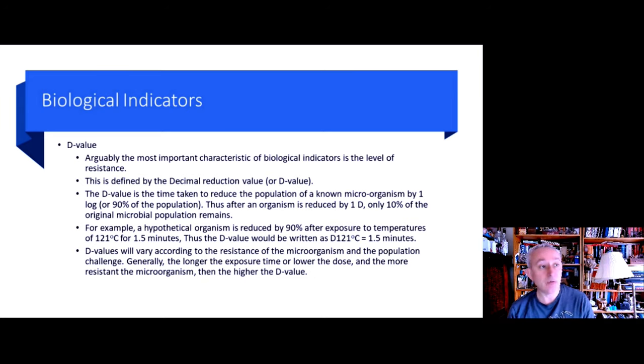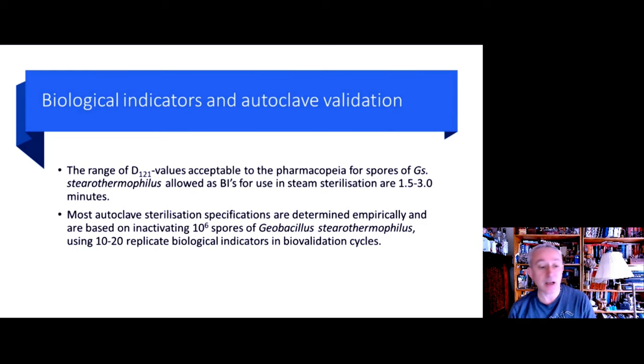Now, thinking about an autoclave for autoclave validation, biological indicators are key for assessing the efficacy of the autoclave. The range of D121 is recommended by the pharmacopoeia, so the standard temperature for evaluating an autoclave is 121 degrees Celsius. The European pharmacopoeia guides us to use biological indicators made from spores of Geobacillus stearothermophilus with a D value of 1.5 to 3 minutes. Most autoclave sterilization processes are then determined empirically by the time taken to inactivate 1 million spores of Geobacillus stearothermophilus. Typically, there'd be 10 to 20 biological indicators placed in an autoclave cycle.